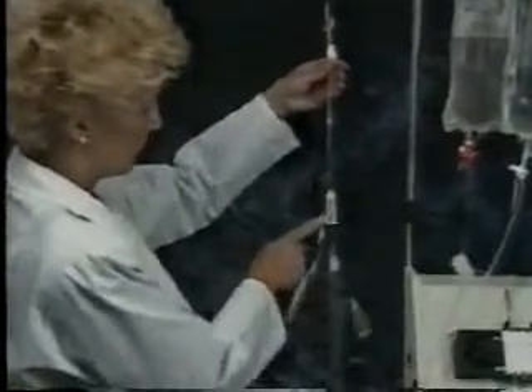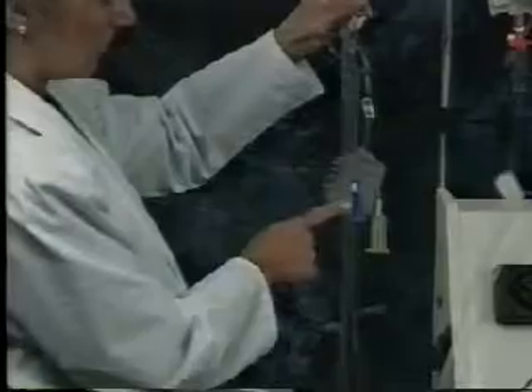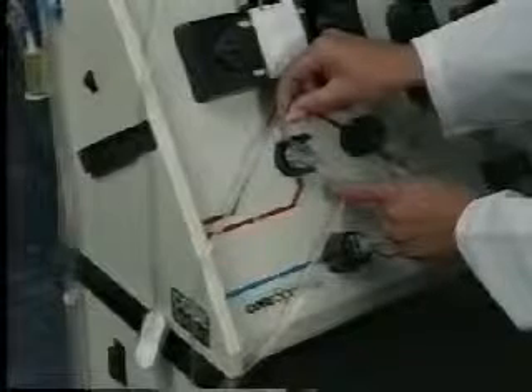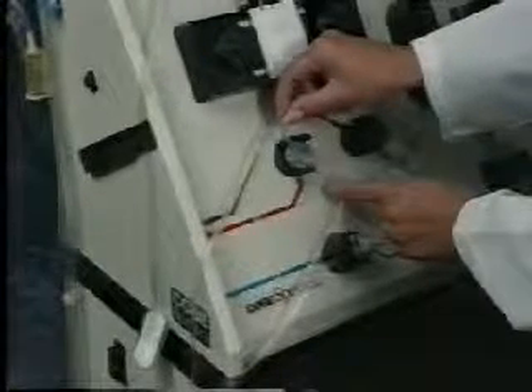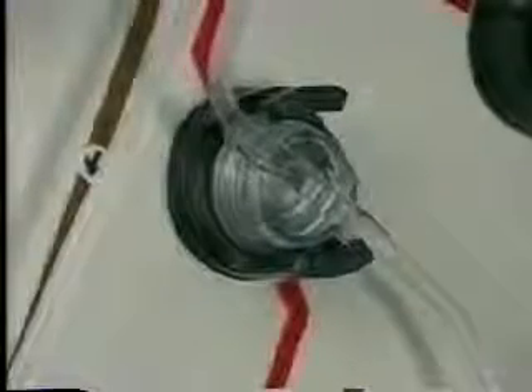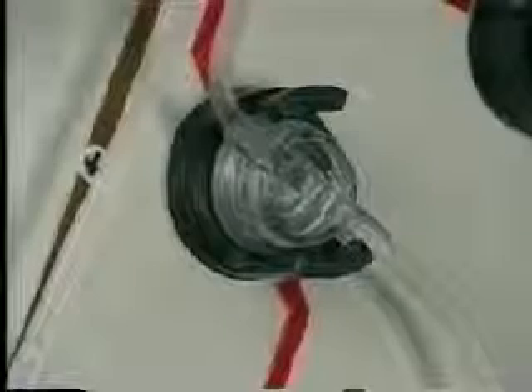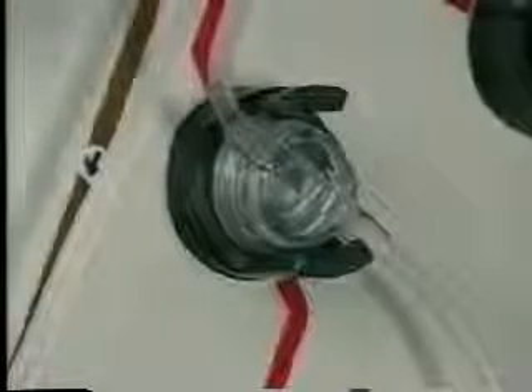Welcome back. You were troubleshooting the access pressure error alarm. This alarm will occur if the access line clamps are open or the access saline roller clamp is closed. Verify these clamps and press the Continue key to clear the alarm. This alarm will also occur if the access pressure sensor was not properly loaded or if the access saline roller clamp was open before the pumps were loaded. Remember, if fluid is in the access line, you cannot simply remove the access pressure sensor and reseat it. Doing so causes the diaphragm to move out of position. We will now go through the steps to reposition the diaphragm. This is also covered in the Recovery Procedures section of your operator's manual.